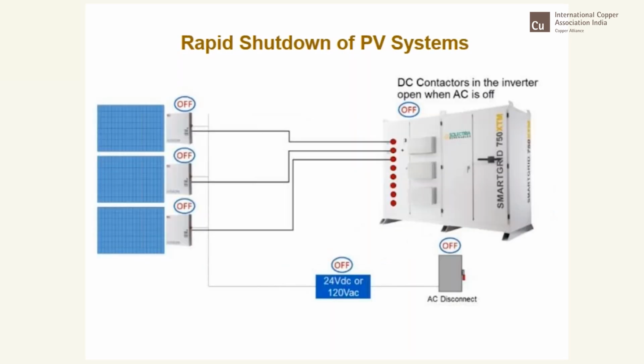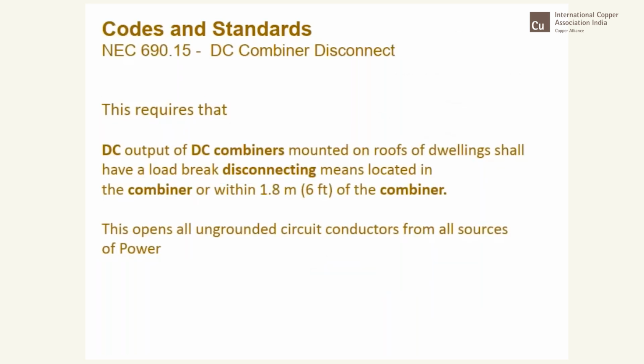So this is in a large power system, a power plant. As soon as you shut down the inverter output and the grid is disconnected, the inverter senses no AC voltage, so it shuts down, and immediately a sequence of shutting down takes place. Then we have the third one, which is again relevant to this, that is 690.15. It requires the DC output of the DC combiner box. As I was telling, combiner boxes are very high potential sources for fire accidents. That is why they have specifically defined codes for combiner boxes also.